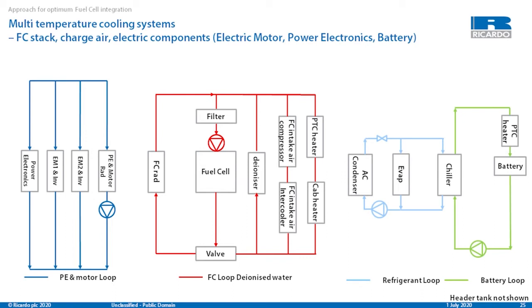On the right-hand side is an example of a battery system that requires a combined heating and cooling network to maintain operating limits. A chiller is shown here, but another possible configuration could be a water-air heat exchanger, depending on where the battery is operated. This is important because batteries have very tight tolerances on temperature control. They're like people in many ways - if it's too hot they don't work well, and if it's too cold they don't work as well, so engineering is required to ensure good performance.